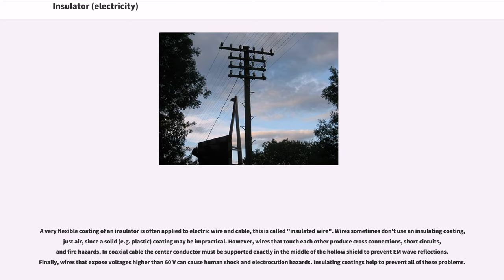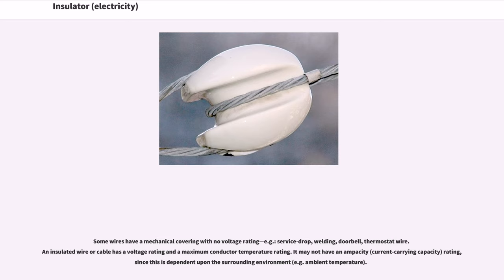Insulating coatings help to prevent all of these problems. Some wires have a mechanical covering with no voltage rating, for example service drop, welding, doorbell, and thermostat wire. An insulated wire or cable has a voltage rating and a maximum conductor temperature rating. It may not have an ampacity rating, since this is dependent upon the surrounding environment, for example ambient temperature.